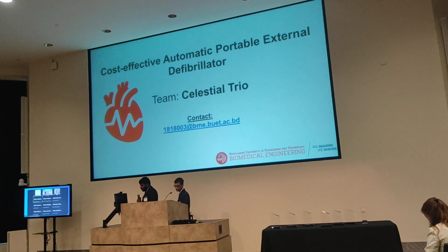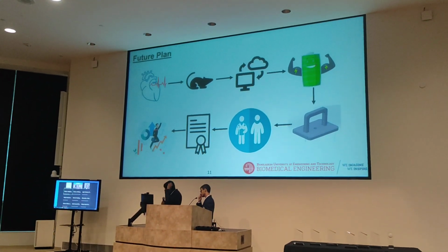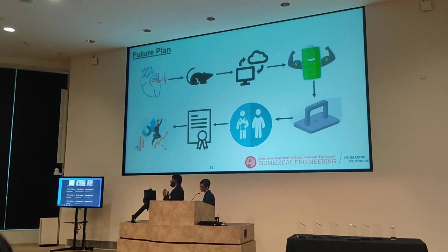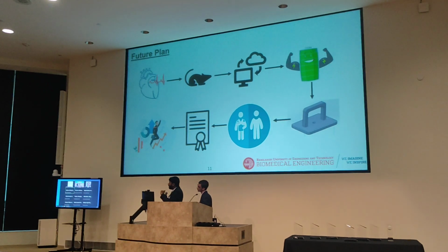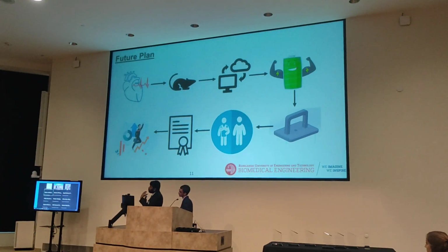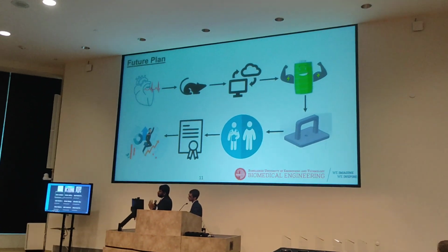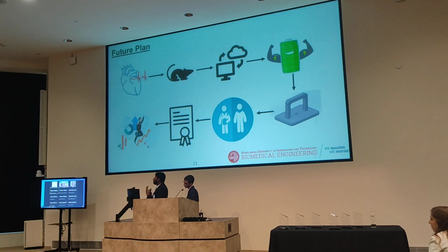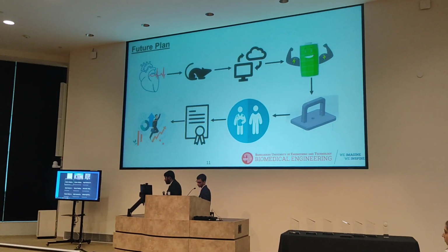Our main plan for children, as we have already said, is basically a weight-based algorithm. So when it is children, the weight will be less and the pad size will be changed according to the children's physical morphology. The pad you are seeing here is only an adaptation of a prototype to show what we are doing to others.